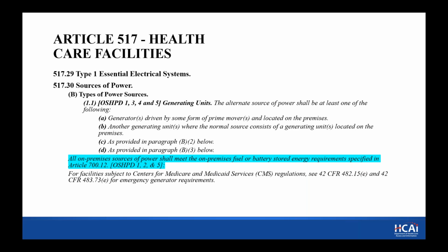That requirement is 4 hours for MOBs, 6 hours for SNFs, 96 hours for hospitals, 6 hours for ambulatory care, surgery centers in MOBs. We'll find, and lots of discussion, there is a new PIN 74, which increases the requirement for on-site fuel storage or provisions for operation of on-site emergency power generators for SNFs.